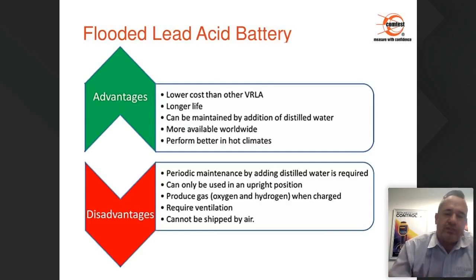Disadvantages: you need to periodically maintain these batteries by adding distilled water. They can only be used in an upright position because they are filled with electrolyte. They produce oxygen and hydrogen gas when charged, so we need ventilation while recharging, and we cannot ship them by air for obvious reasons.